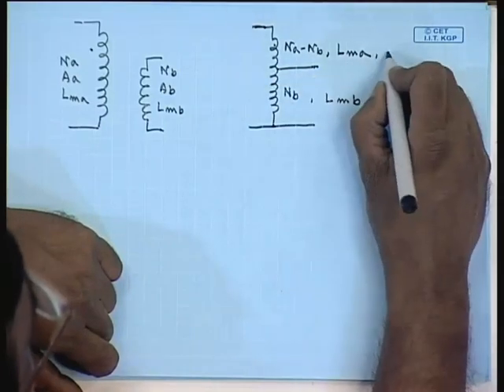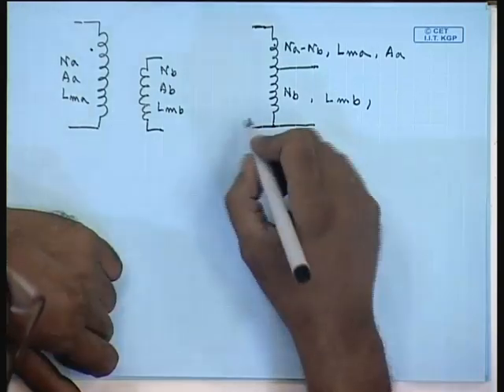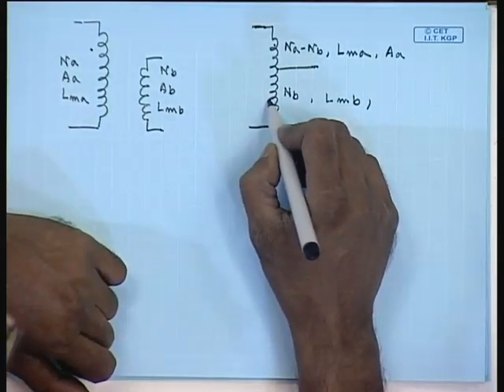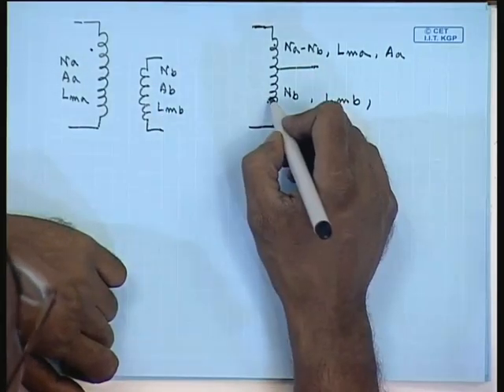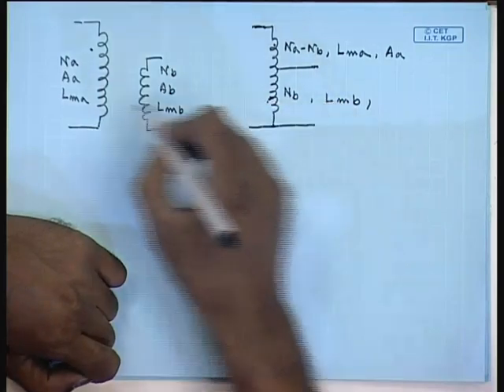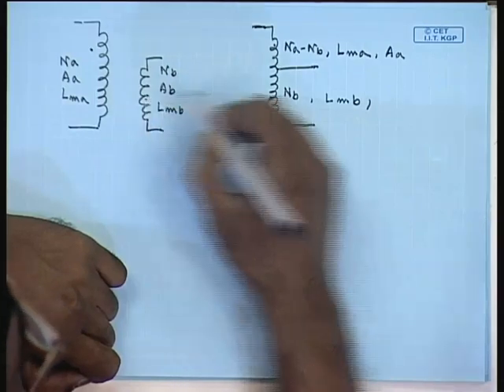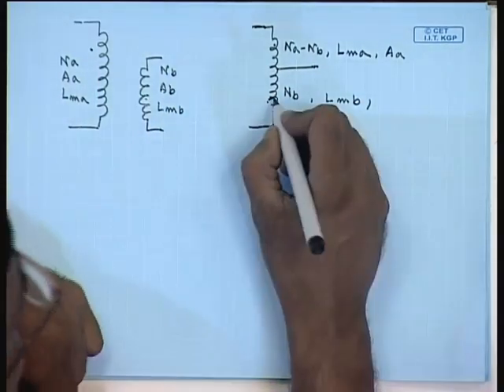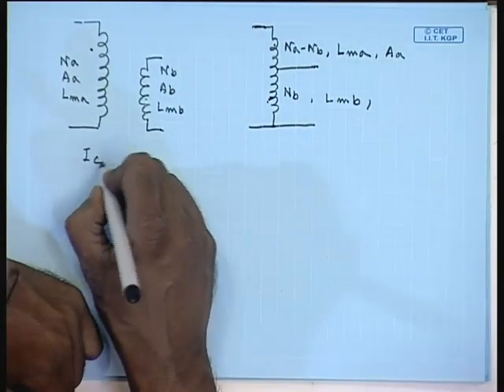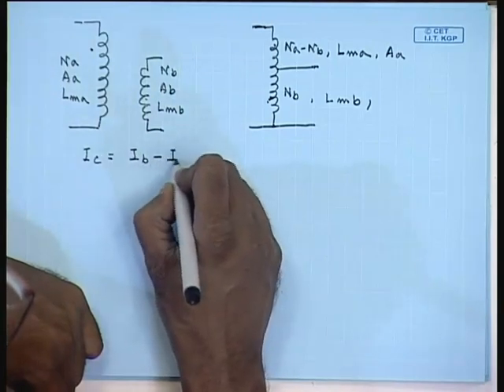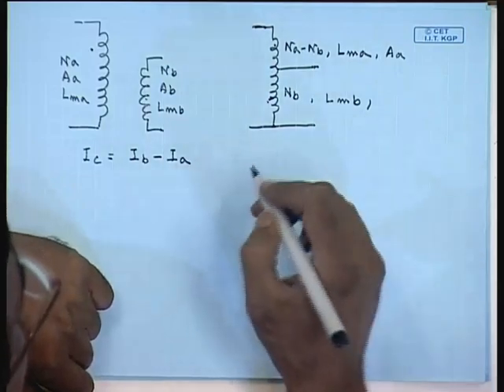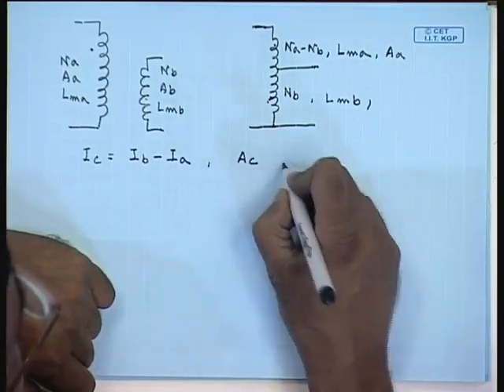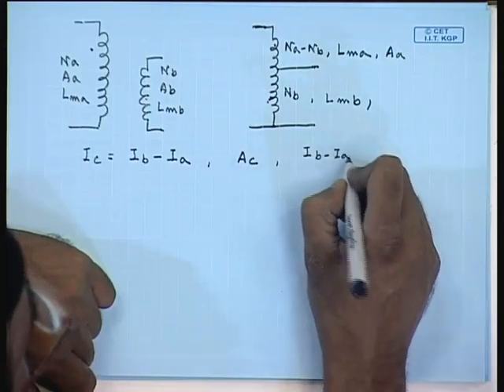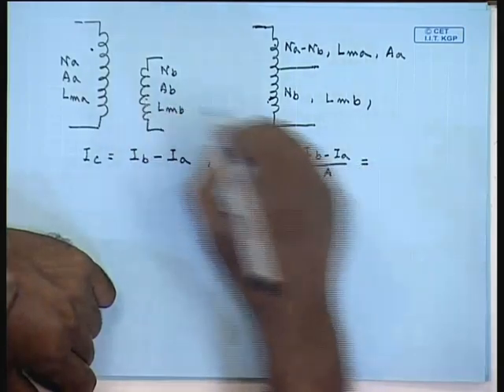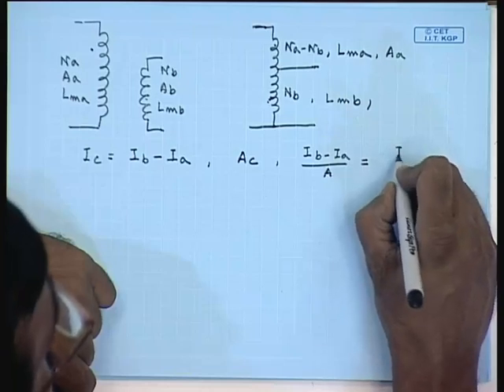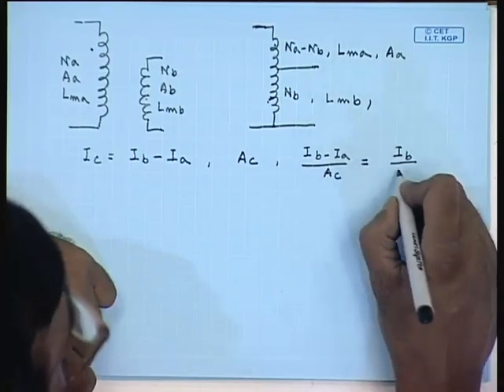So, this part has a cross sectional area of AA. However, the current carrying capacity of this part of the auto transformer is IC, which is IB minus IA, whereas for this it is IB. Therefore, the current carrying capacity of the lower part of the auto transformer is IC equal to IB minus IA. So, if this part has a cross sectional area of AC, the current density is IB minus IA by AC. This should be same as the current density of the LV winding of the two winding transformer. So, this should be equal to IB by AB.